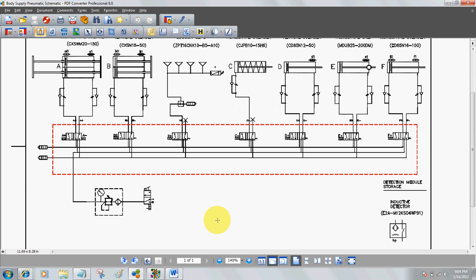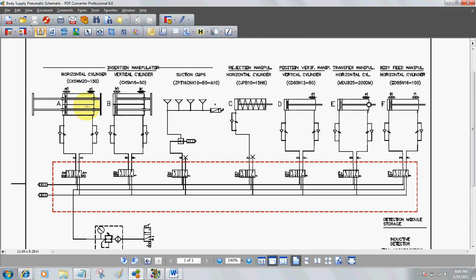Let's take a brief look at the pneumatic schematics. These are our actuators on the station: horizontal cylinder, vertical cylinder, etc. Each cylinder has a specific purpose. The prox switches on the ends detect the magnets inside the cylinders — as the cylinder moves back and forth, the sensor is triggered and sends input information to the PLC. Note there are no inputs on the rejection cylinder. The position verification cylinder has only one input, so we only know it's extended. The transfer manipulator also only has one input. The body feed manipulator has two prox switches, so we know if it's extended or retracted.